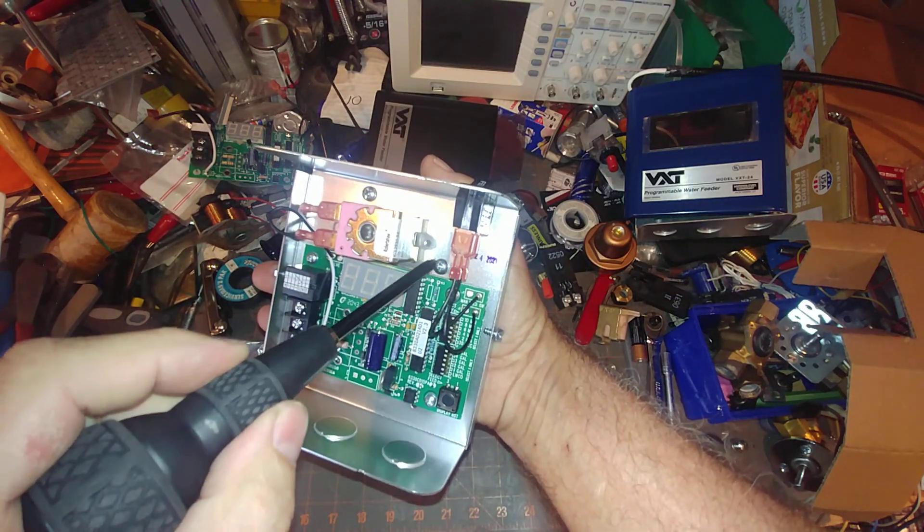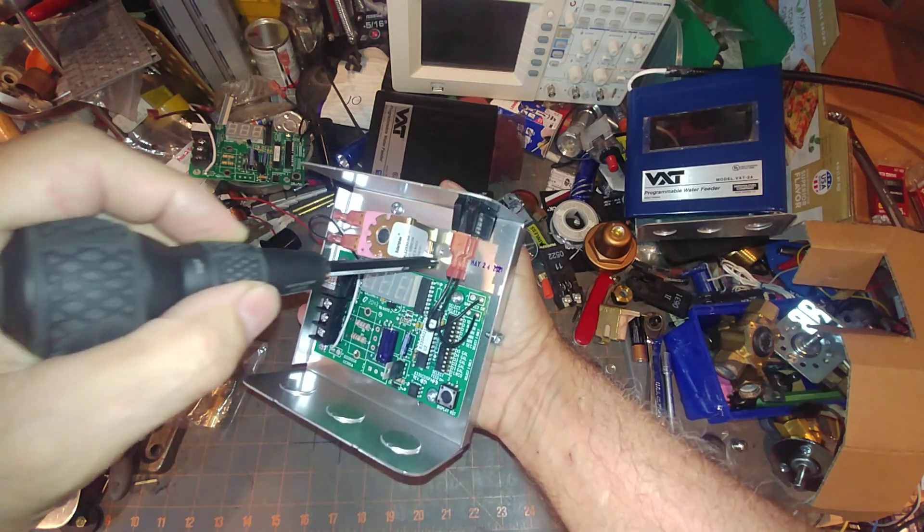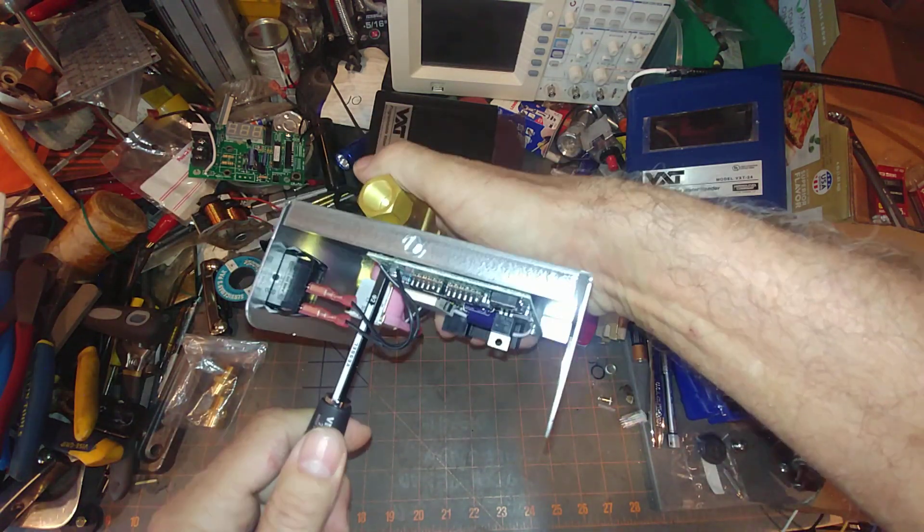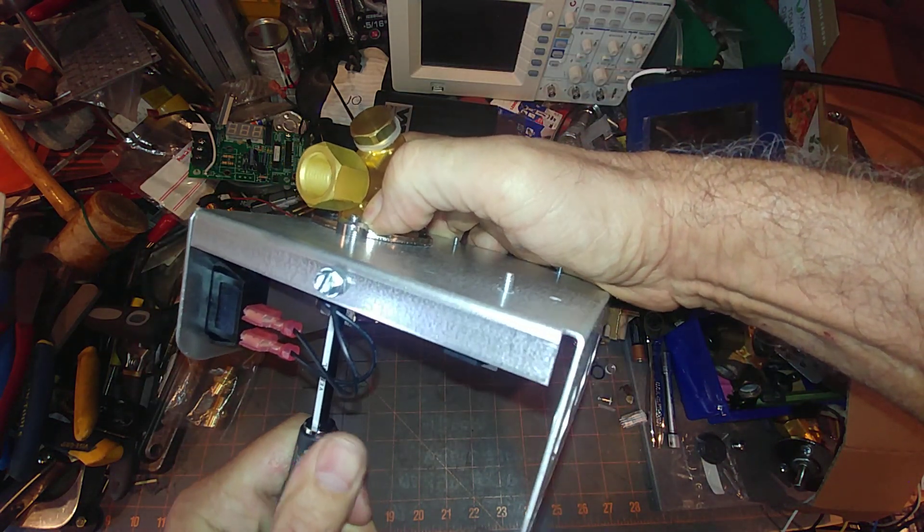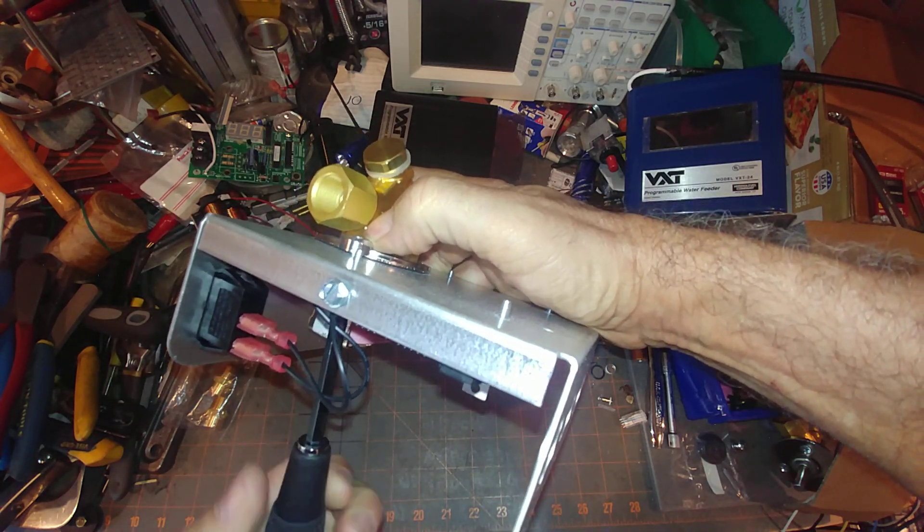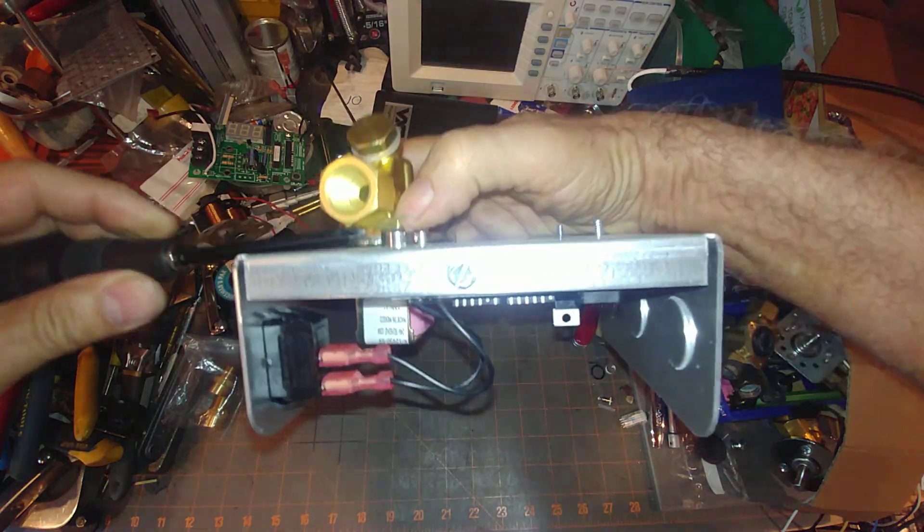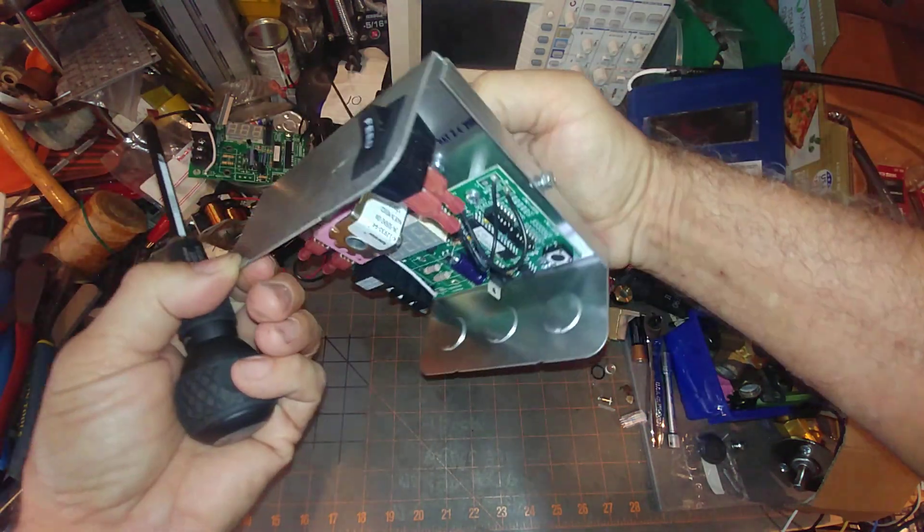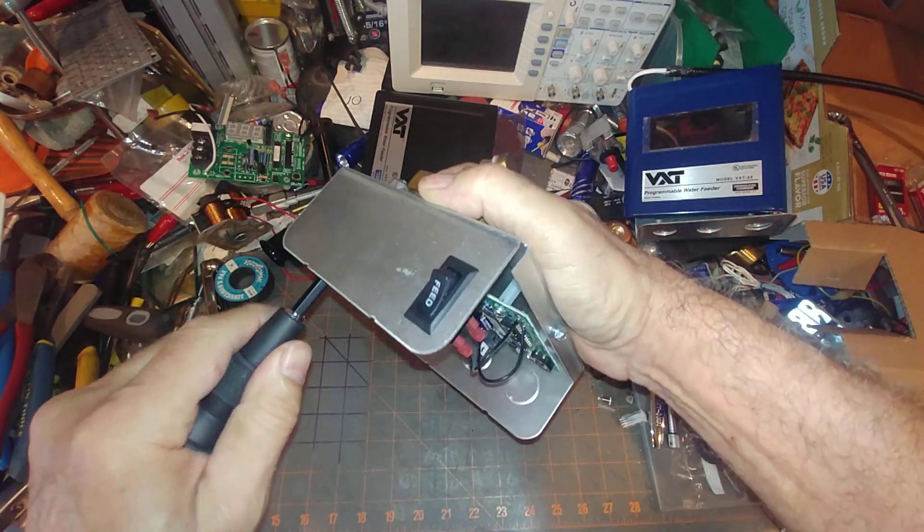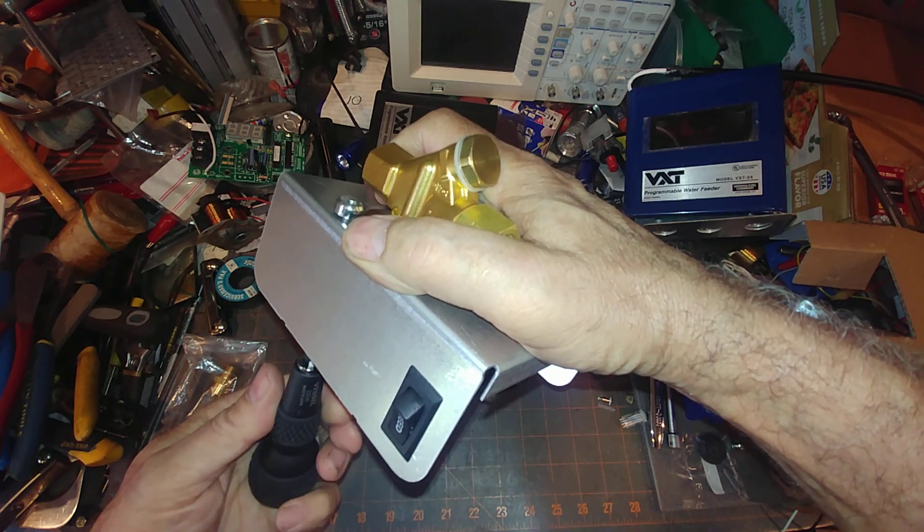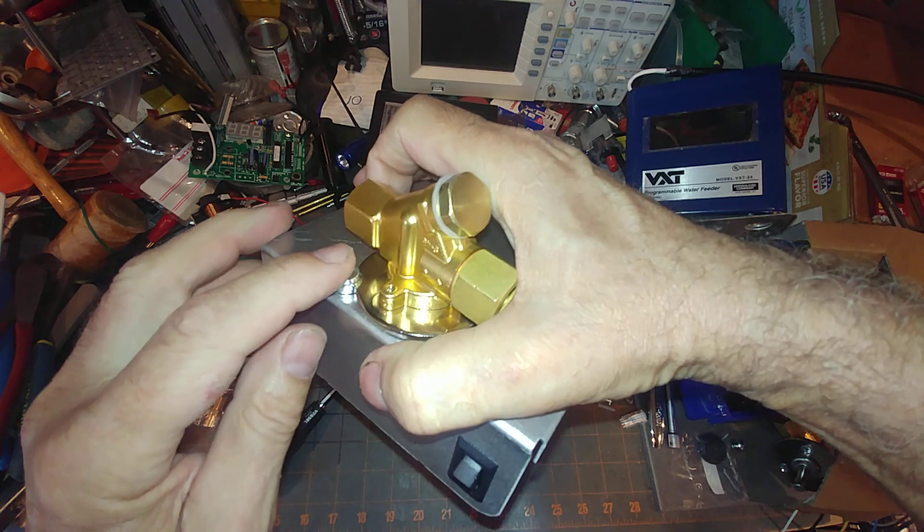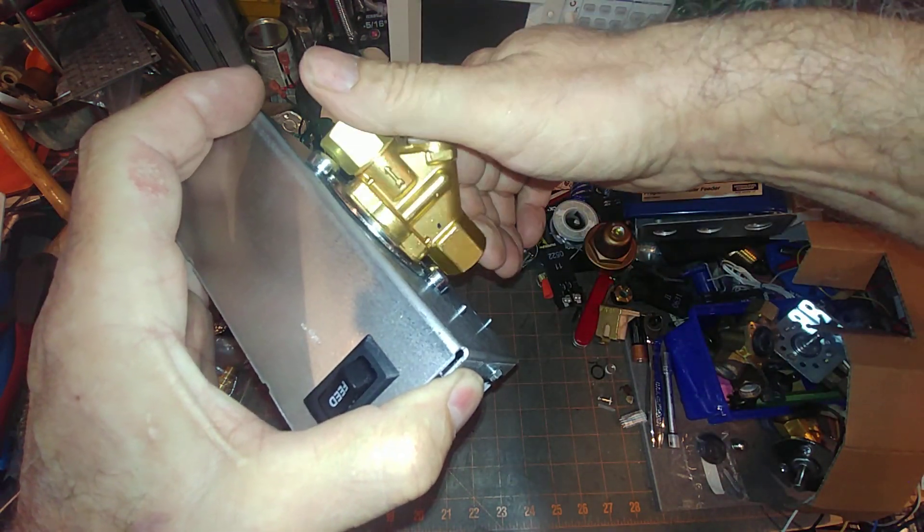You've got two Phillips head screws there now. And you want to loosen them so that this is flush because otherwise it'll catch the valve when it moves. So you take this down, and you don't want to back it out too far because you don't want to lose these clipped washers. But that's as far as you want to back it out, just like that. And then now this is infinitely adjustable.